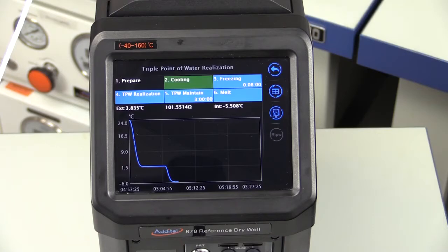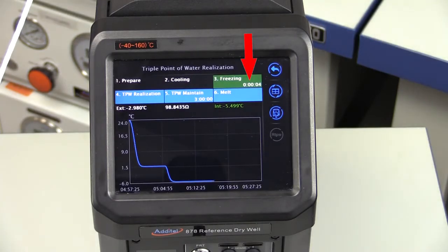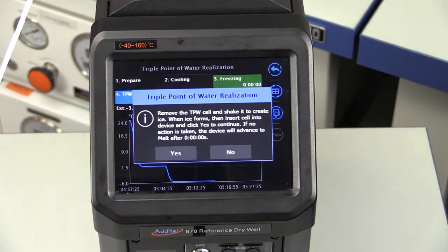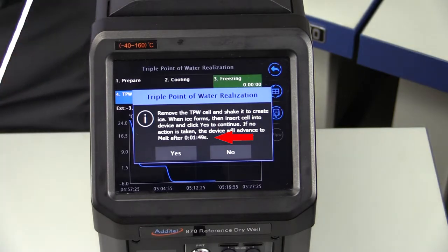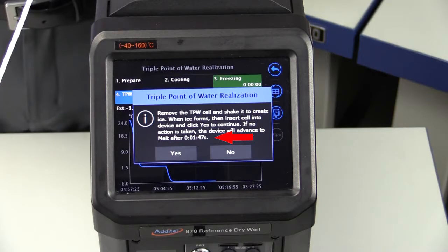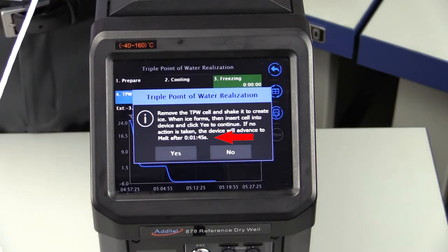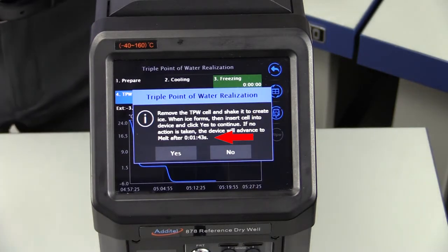When the cell is at the freezing set point, a 10-minute countdown will begin. Once the 878-160 has supercooled the cell, it will audibly beep letting you know when the TPW cell is ready to be realized. The ADT program will count down for 2 minutes to allow you time to remove the cell and realize the triple point. If no action is taken at the end of the countdown, the ADT878 will heat the cell back up to protect it from potentially breaking if left at minus 5 degrees C for too long.